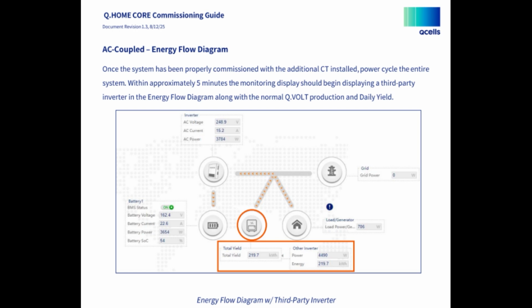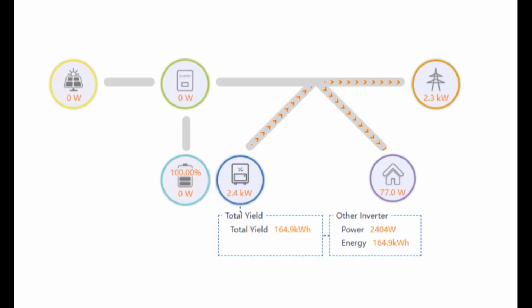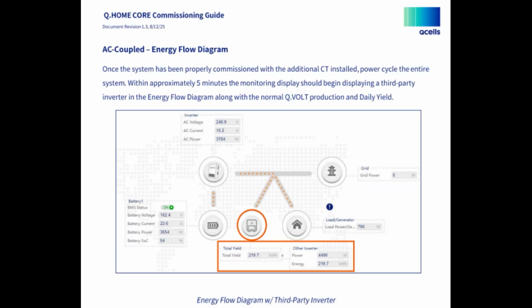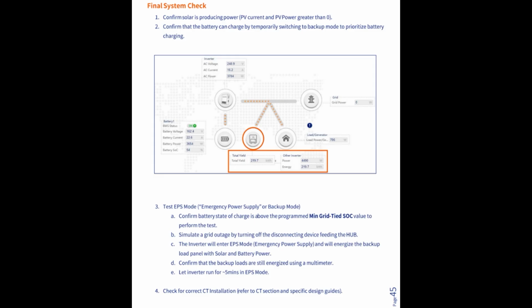Connect to the inverter locally or check the monitoring data to ensure the generation icon appears on the energy diagram for the AC-coupled solar system. The original PV icon will remain on the diagram with no data being reported for DC energy. The energy diagram should reflect the batteries charging from the solar-generated energy. Test the operation of EPS mode by turning off the disconnecting device feeding the hub. The system will enter EPS mode and will energize the backup load panel with solar and battery power.